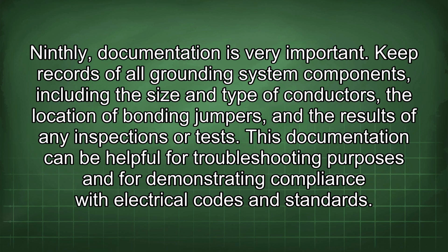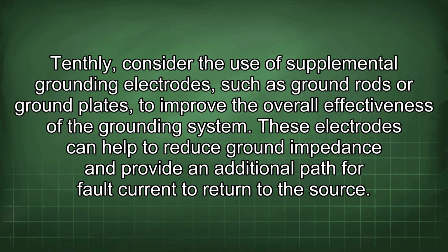This documentation can be helpful for troubleshooting purposes and for demonstrating compliance with electrical codes and standards. Tenthly, consider the use of supplemental grounding electrodes, such as ground rods or ground plates, to improve the overall effectiveness of the grounding system. These electrodes can help to reduce ground impedance and provide an additional path for fault current to return to the source.